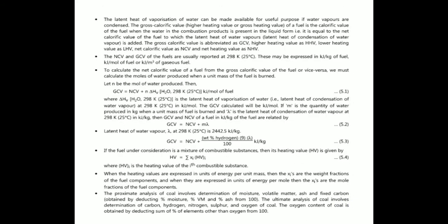The latent heat of vaporization can be made available for useful purposes if the water vapors are condensed. The Gross Calorific Value (GCV), or higher heating value, is the calorific value when water in the combustion product is present in liquid form. It equals the NCV plus the latent heat of condensation of water vapor. So: GCV = NCV + latent heat of vaporization of water vapor.